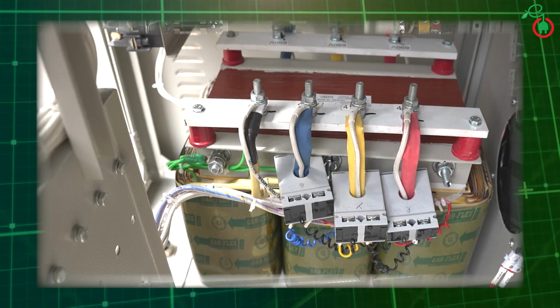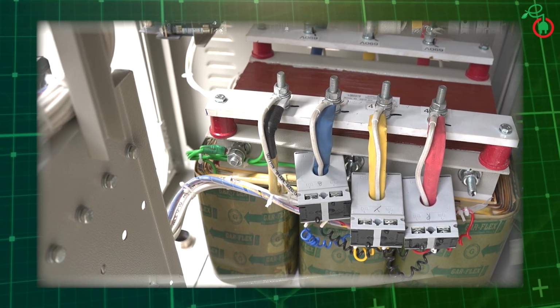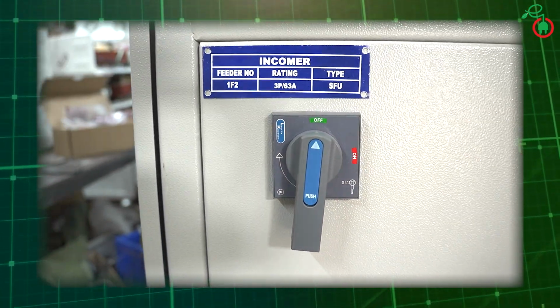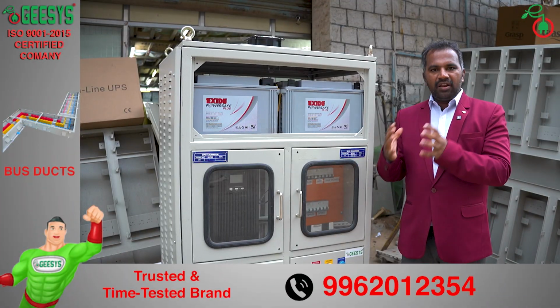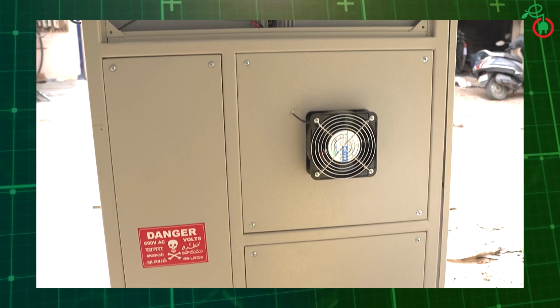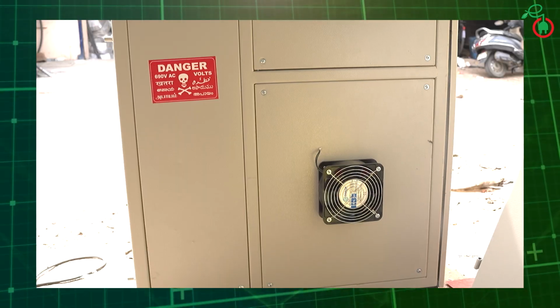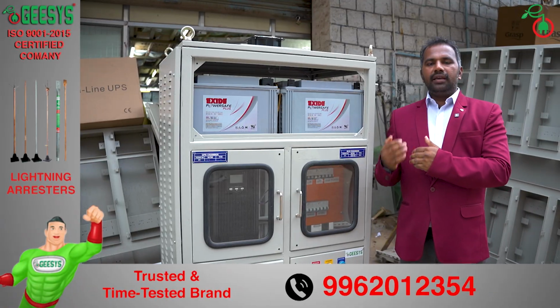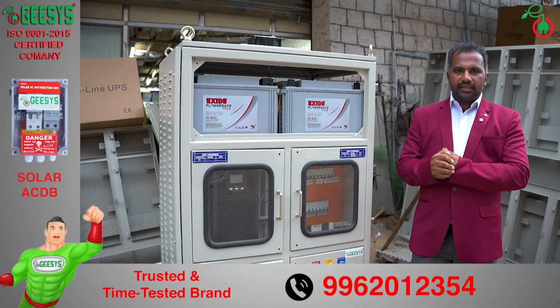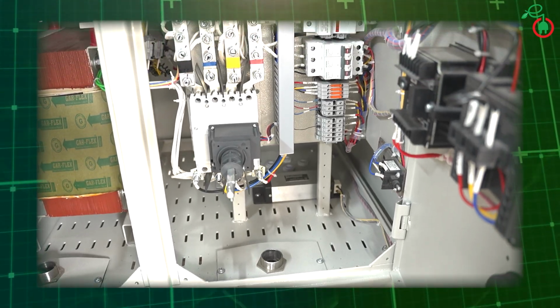That auxiliary transformer is protected with a 63 amp SFU, that is a switch disconnect fuse unit, and the auxiliary transformer manufactured by Geesys comes with a thermal cutoff device. So when there is a temperature rise, the fans will automatically be switched on, and the step down voltage from the auxiliary transformer will be given to a power distribution board.